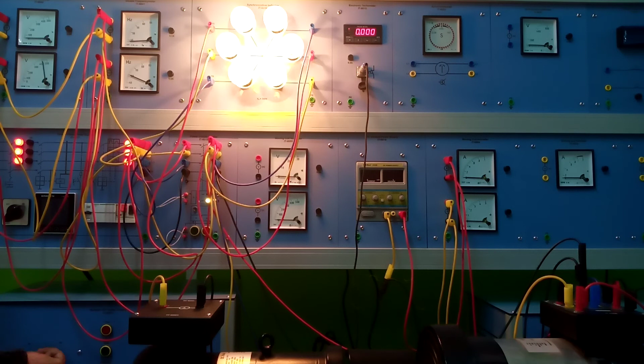So you saw that two lamps were equally bright and one lamp was off. This means that the yellow lamp connection here we didn't change. So two lamps were equally bright and one lamp was off, which shows that you can now turn on your synchronization power circuit breaker.